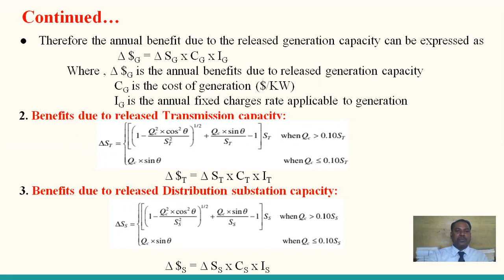Benefits due to released generation energy losses. Yes, it is obviously 100% correct. Why? Because capacitors will minimize the voltage drops and reduce the energy losses. Why? Because power factor and current are inversely proportional to each other. As the power factor increases, the magnitude of current reduces, resulting in reduced losses. Due to the capacitors, the benefit here is reduced energy losses.